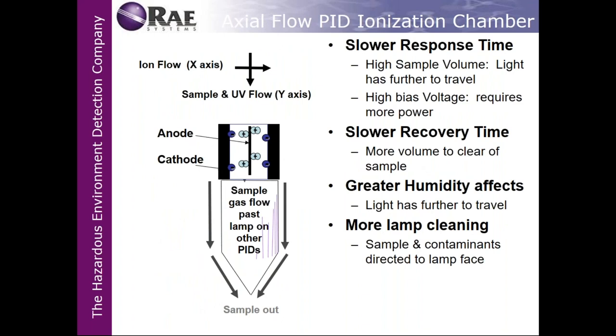This picture shows a little bit more technical drawing of what I showed you in slide 3 or 4, talking about slow response times. When you have a high sample volume, the light has further to travel. High bias voltage requires more power. Slow recovery time. This is important because when you get a high hit with a PID, you'll notice PIDs take a little bit longer to come down. Let's say it shoots up to 560, then you take it out of the environment, it goes to 360, 280, 160, 80.